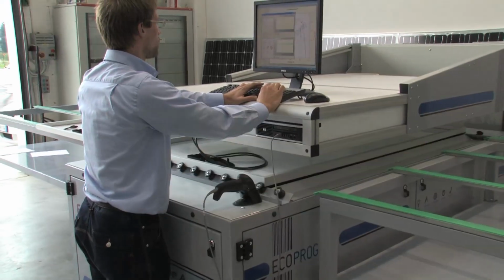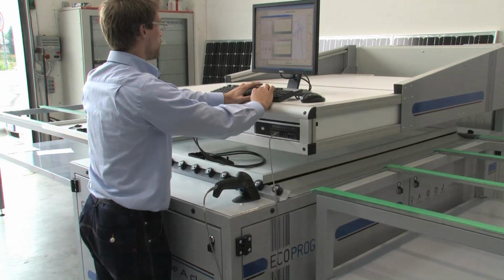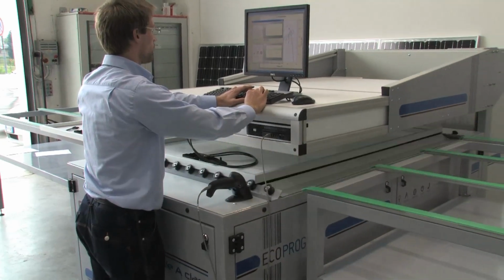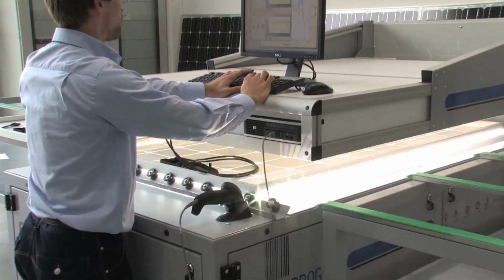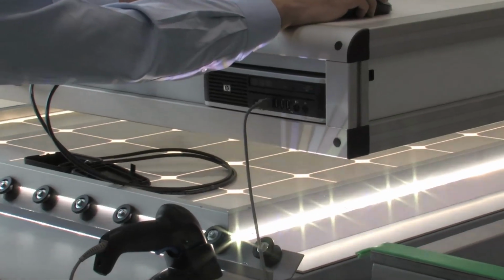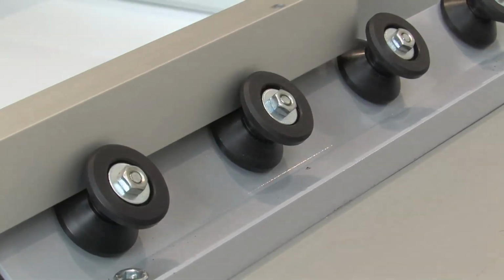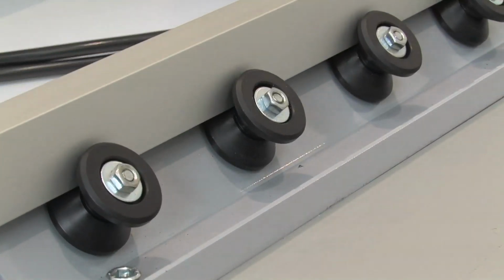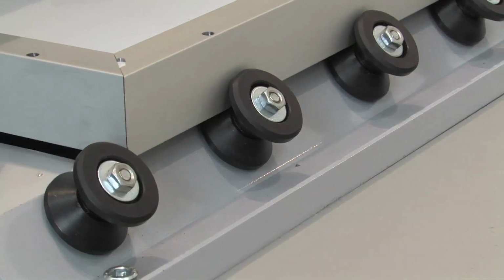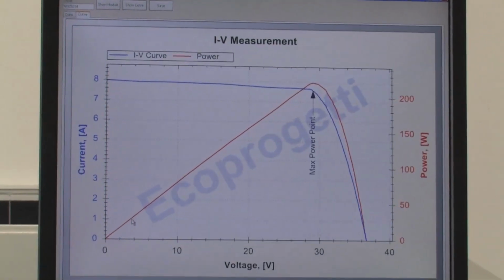This characteristic includes also the possibility to personalize the test impulse duration that can be extended also to more than 10 seconds, maintaining the radiation stability with a maximum variation of 0.18%. This feature that is not possible to obtain with standard flash simulators is very useful to prevent that the measurement is affected by the capacitive effects of the module. A personalized pulse is very useful both for crystalline products as well as new technologies like thin film and back contact solar cells.